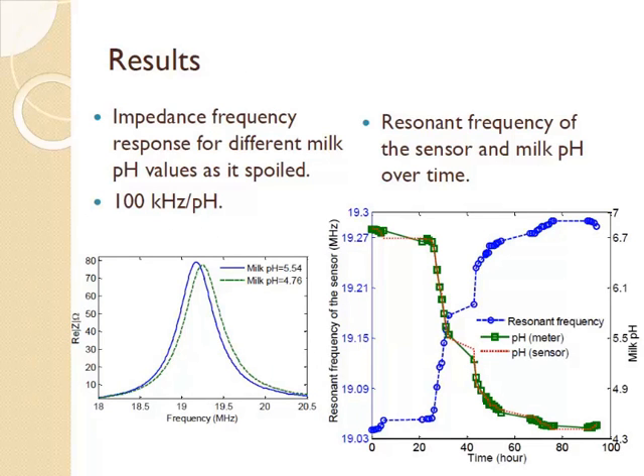On the left, you can see the impedance frequency response for two different milk pH. You can see that in a fluid medium, we have a very good quality factor for our response. The green curve is the pH measured by the commercial pH probe over the 3 days, and the blue curve is the resonant frequency of the sensor. You can see that the resonant frequency changed almost the same way the pH of the commercial probe was changing.